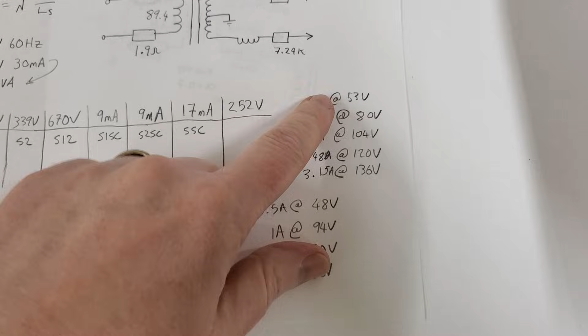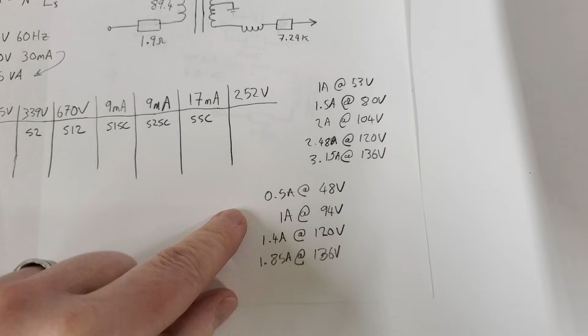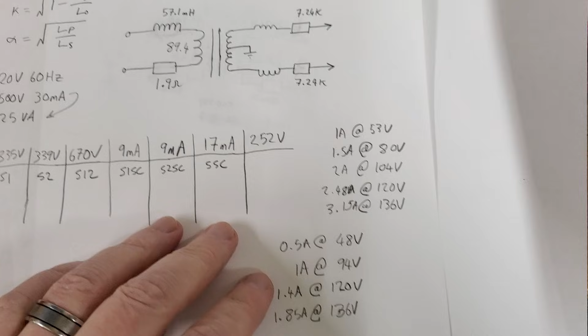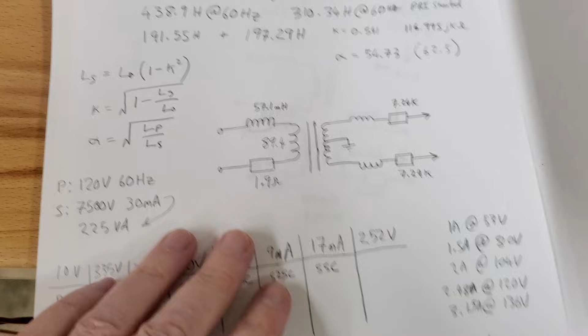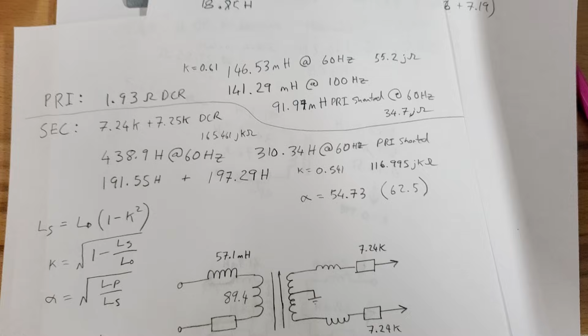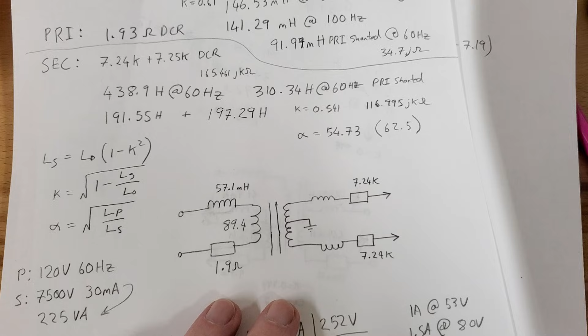So that was kind of interesting. That's with both high tension outputs shorted together, and this is with just one shorted. Kind of what you'd expect, right? Half the output voltage, so half the current and the reflected. But the more I did the math on this transformer, I'm convinced that either the capacitance here is messing up my meter, or in general my meter just doesn't like measuring into this. Well, the phase angle is not actually that crazy. Like if this was like 1,000 henries, a 4.7k-ish or 7.2k resistor each side of that wouldn't be ridiculous.